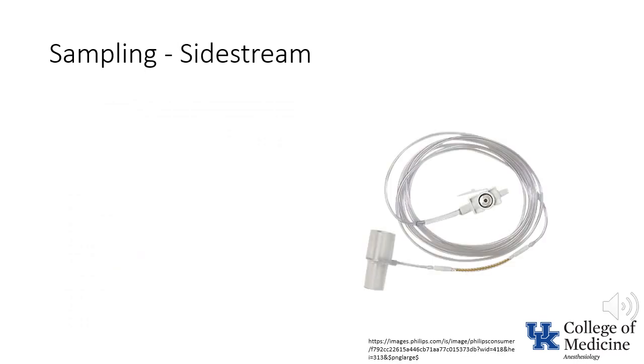Sidestream sampling is the technique that has the greatest amount of acceptance. The primary advantages and disadvantages are exactly the opposite of those of mainstream sampling. Because the sample has to be aspirated from the circuit to the measurement device, there is a significant time lag before results are available. On the other hand, the sampling device weighs next to nothing and so is not likely to result in displacement of the tracheal tube.